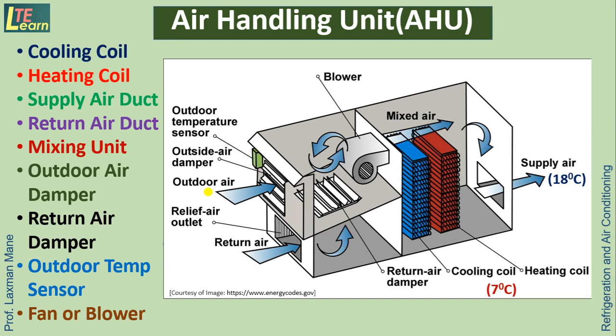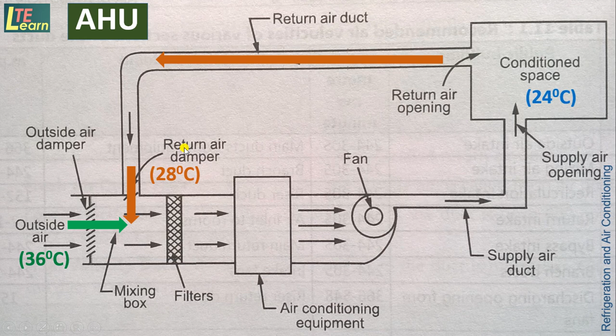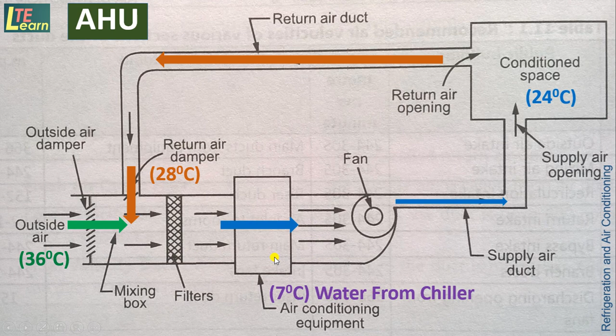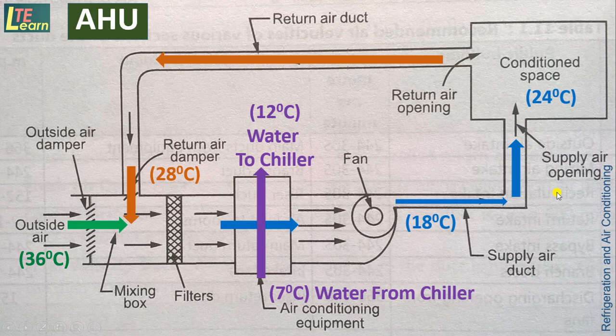So this air, by absorbing the heat of occupants, gets warm. This warm air is carried via the return air duct. This air is at 28 degrees Celsius. Here, outside air, that is fresh air, which is at approximately 36 degrees Celsius, is mixed with return air in the mixing box. After filtration, this air passes over the cooling coil, which carries chilled water. Thus, the air is cooled to 18 degrees Celsius. Such conditioned air is supplied by the supply air duct to the conditioned space.